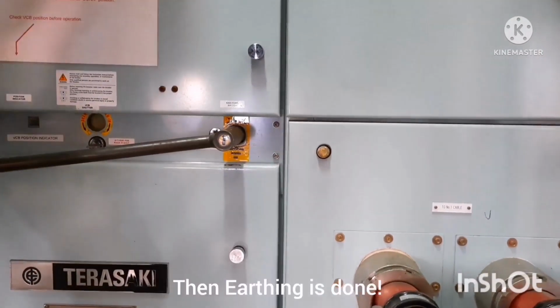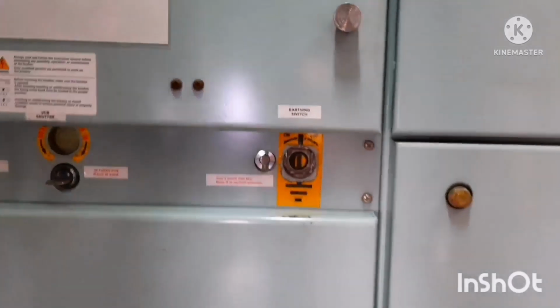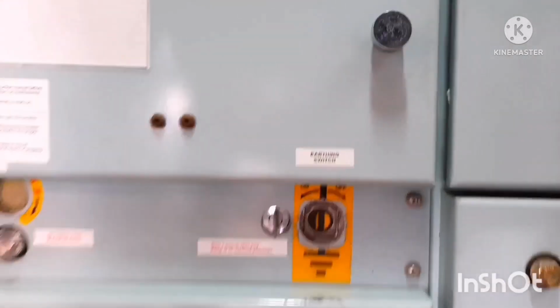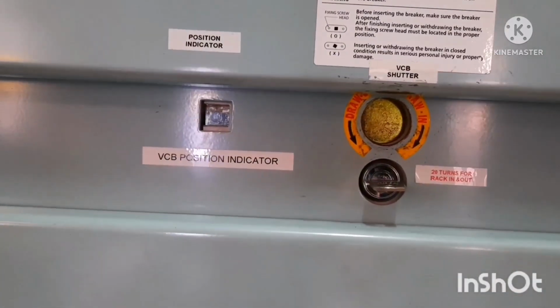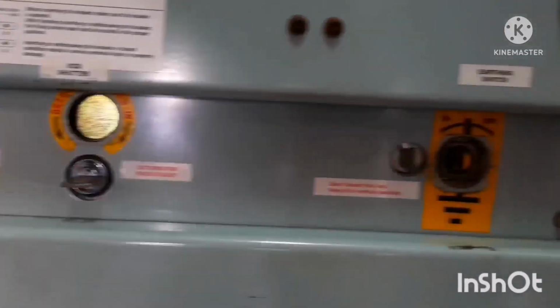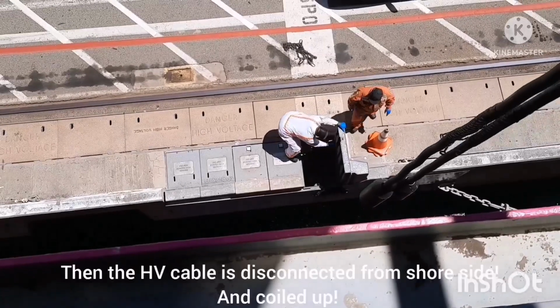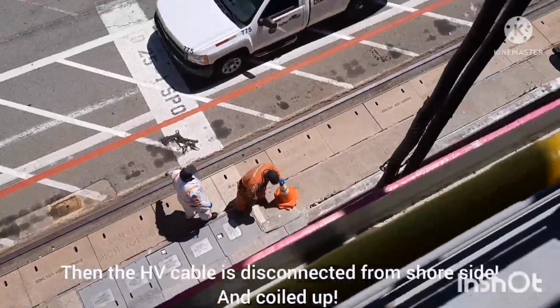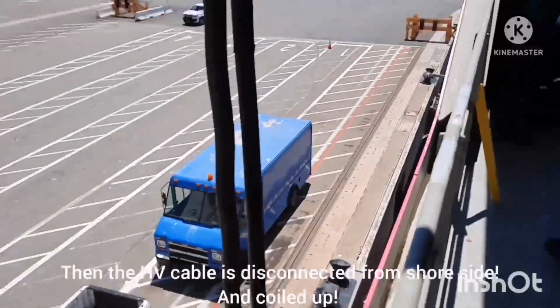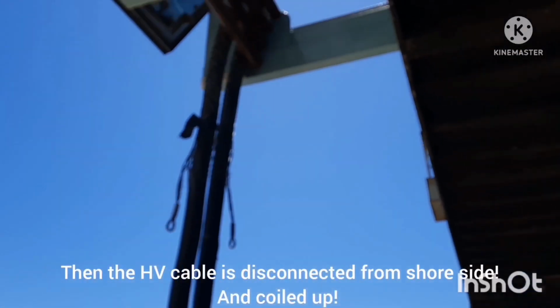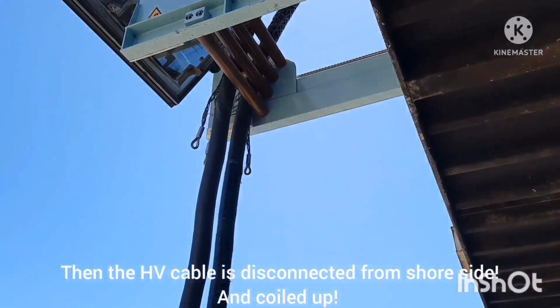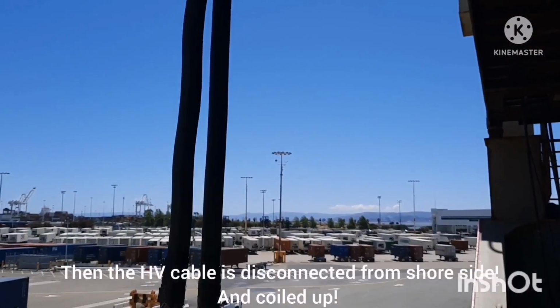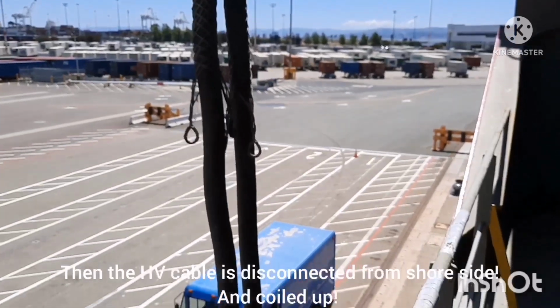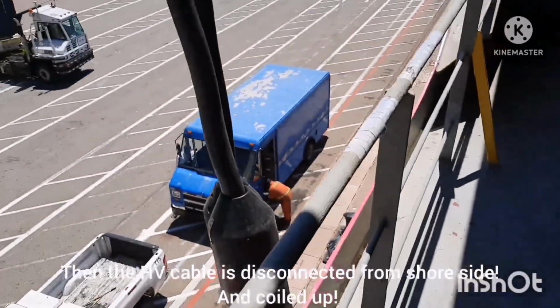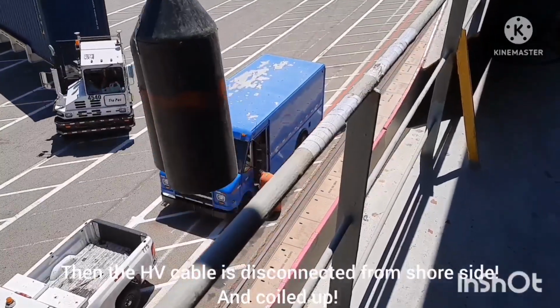Once the earthing is done, you can see the indication of earthing will change. You can see it's vertical, so that means earthing is done, and the VCB position is out already. So these two are done for the shore side. Now the high voltage cable is disconnected from the shore side, and the cable is being coiled back onto the amp container drum. Once this is coiled up, all we need to do is disconnect the high voltage cable from the amp box to the socket.